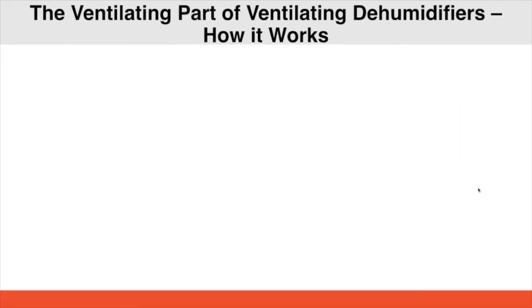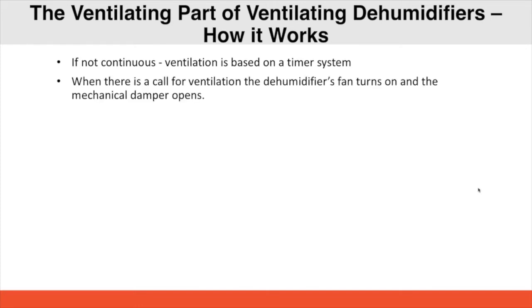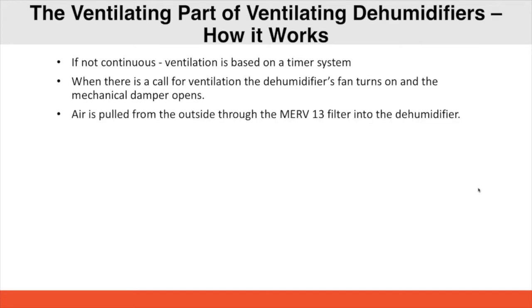So, the ventilating part of how ventilating dehumidifiers work. We get a lot of questions on this as well, so we're going to break it down here. If you're not running continuous, ventilation is then based on a timer system. So you'll have a controller, whether it's our DH3000 controller, or you're integrating our system with a thermostat that provides ventilation control, but you can set it up based on a timer system if you're not running continuous. When there is a call for ventilation, the dehumidifier's fan is going to turn on and the mechanical damper is going to open. Air is pulled from the outside through the MERV 13 filter into the dehumidifier.